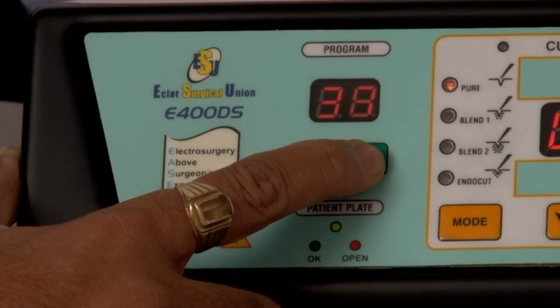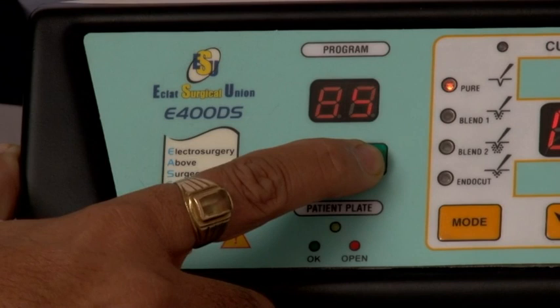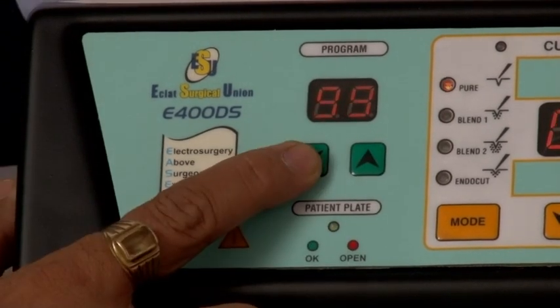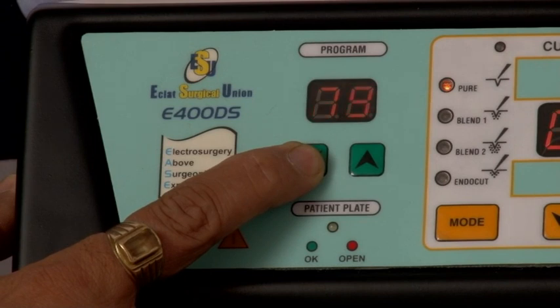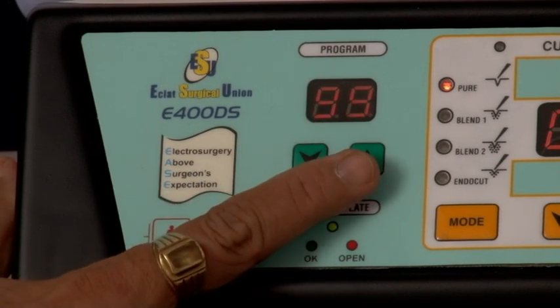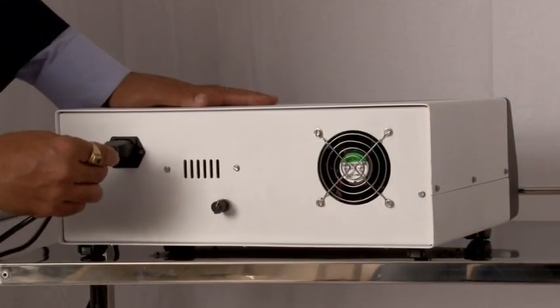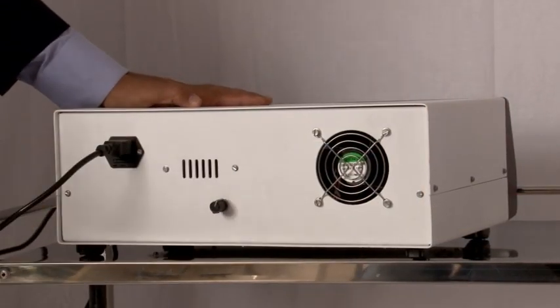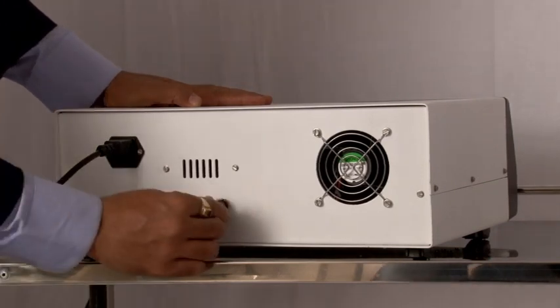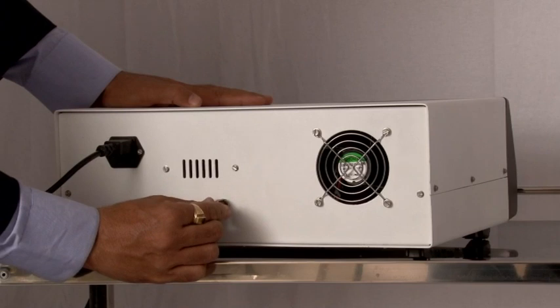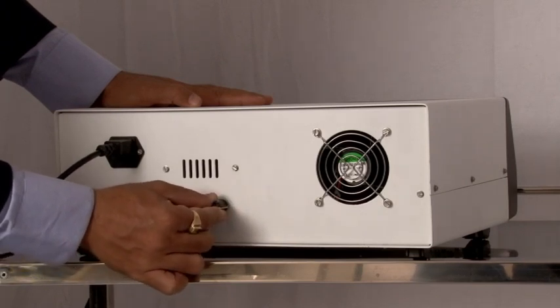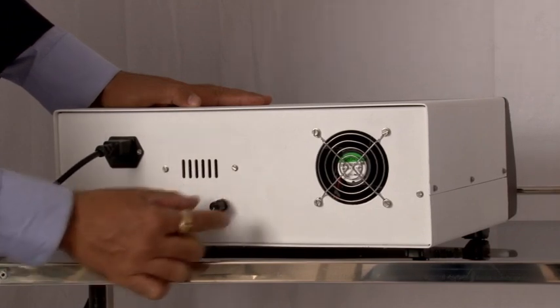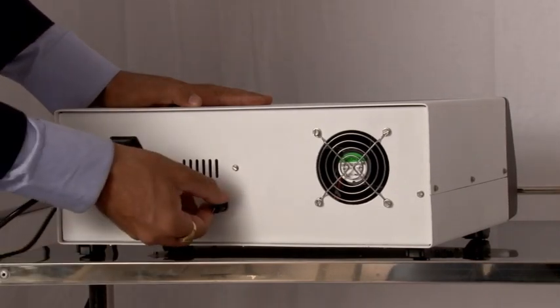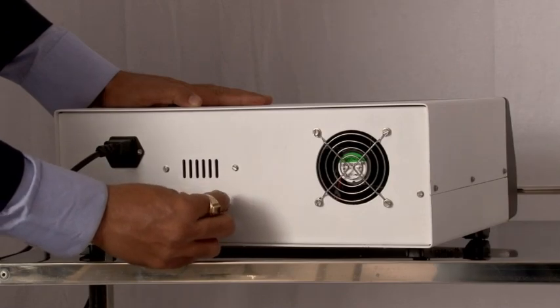A special programming feature is provided with the machine. Power settings of any surgical procedure can be stored by pressing a particular number from program switch and is available at any time after recalling the same number. Total 99 power settings can be stored with the help of program switch. On the rear panel, input power connector and volume control knob is provided. Input power cord is detachable and is very easy to replace in faulty conditions. Volume control knob is provided to increase and decrease the volume of cut, coag and bipolar modes.